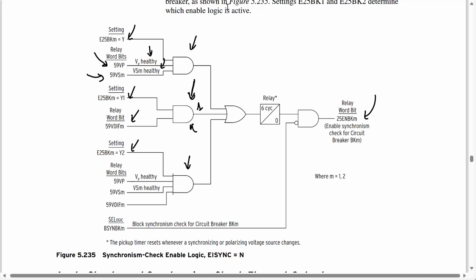And then if we set the enable to Y2, that's sort of a combination of both Y and Y1. As you can see over here, we have this portion, which is the same as just setting that enable to Y. And we also have this portion over here, which is similar to Y1. So what this means is that the voltages must be in a band that we define with the settings and also be within a certain range of each other. So the difference between the two voltages cannot exceed another setting. So again, it's just sort of a combination of Y and Y1. For this example, we're just going to use the Y option.